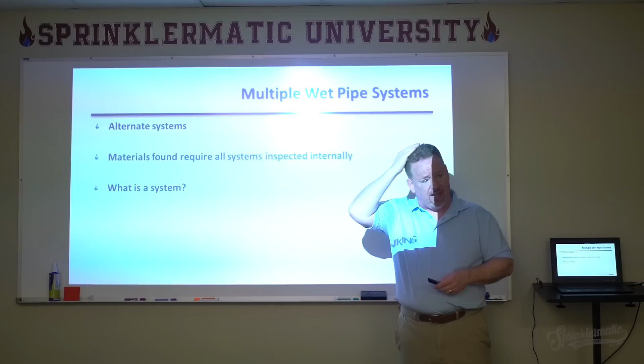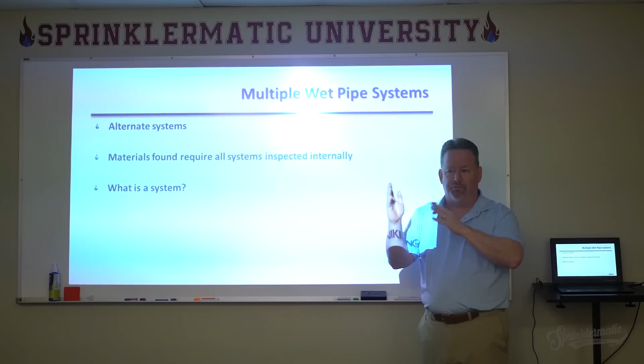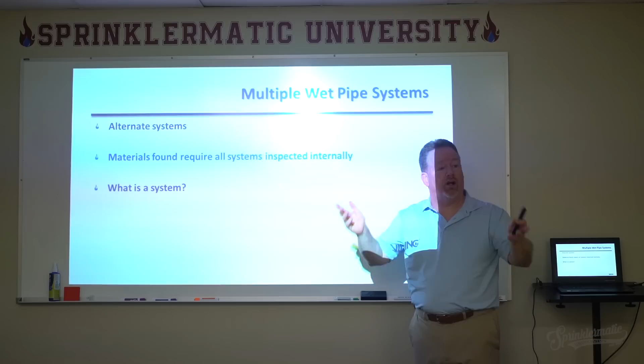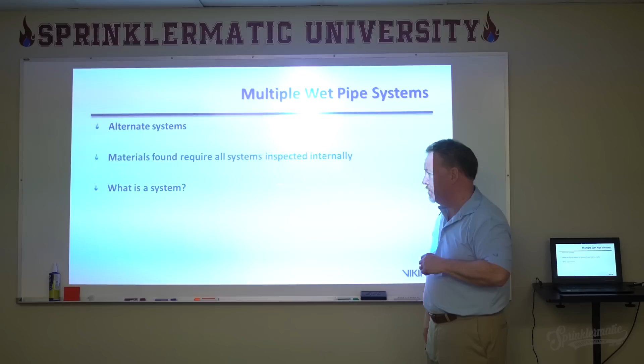Okay, so the big challenge here then is, if I've got multiple wet pipe systems in the building. Let's just say I've got a building with 6 risers protecting a warehouse, a wet pipe system down here protecting our warehouse. I don't have to perform, what NFPA 25 says, I don't have to perform an internal assessment of the pipe on all of the systems every 5 years. I can alternate them. I can go system 1, 3, and 5, and then 5 years later do 2, 4, and 6. Unless I find materials in there during that time, and then I have to inspect all of them internally. Because if I've got a problem in one, chances are pretty good I may have obstructive material somewhere else.